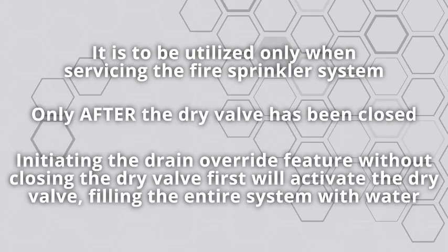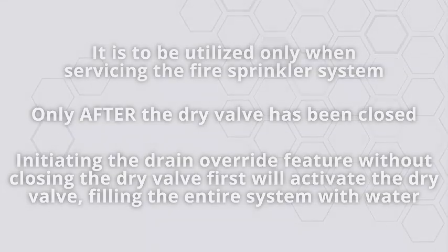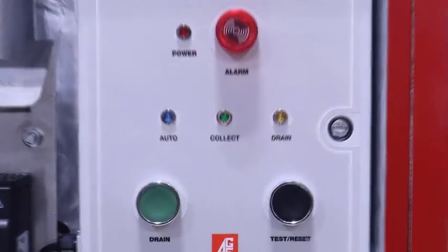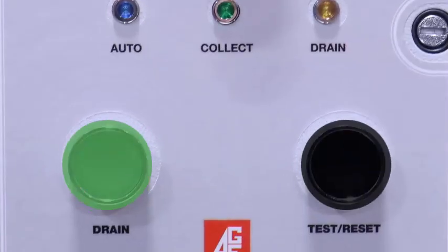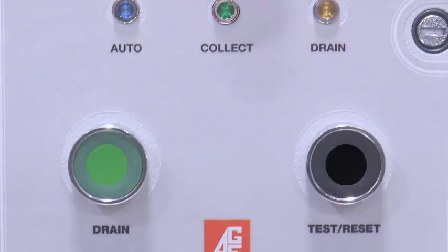Initiating the drain override feature without closing the dry valve first will activate the dry valve, filling the entire system with water. To initiate the drain override, press and hold the drain button and the test and reset button on the control panel simultaneously for 3 seconds.